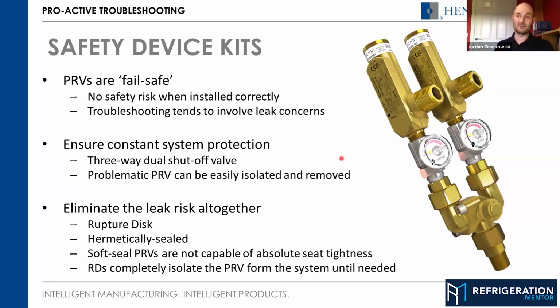But if you think back to what we talked about to do with flow restriction and pressure drop, yes, you're going to open both valves, but you've got half the port either side. So neither valve is going to vent properly because you've restricted the flow. So yes, it should always be one valve or the other, fully seated to one side or the other, never in the middle. Yeah, thanks, Stephen. So now I want to ask some questions, because you had a good point there.